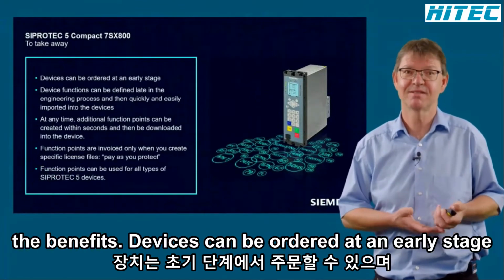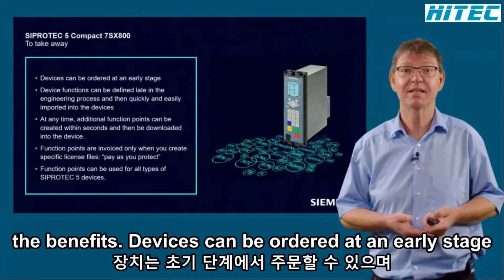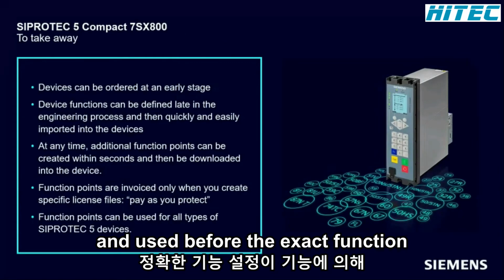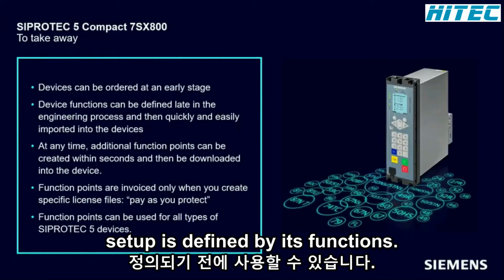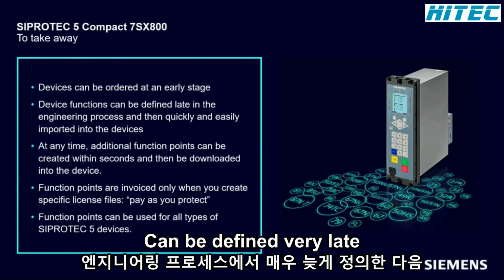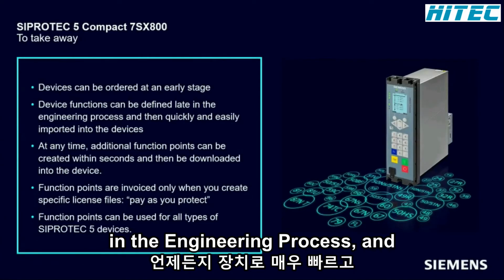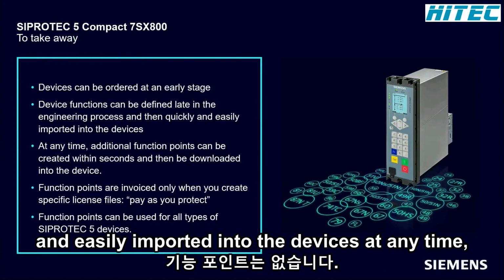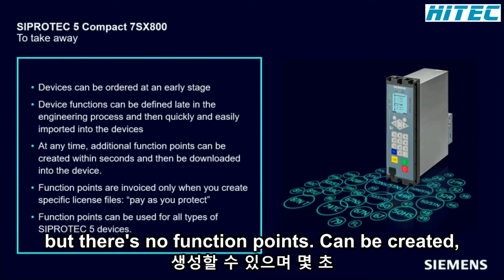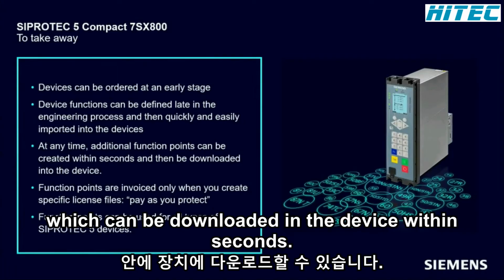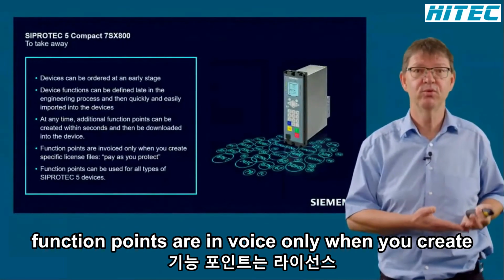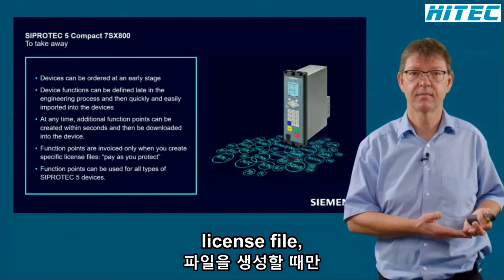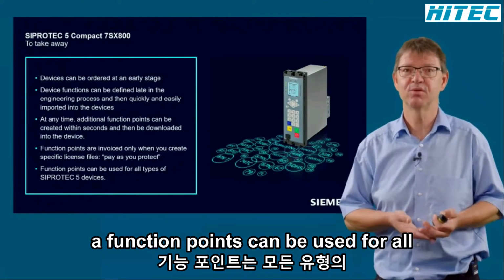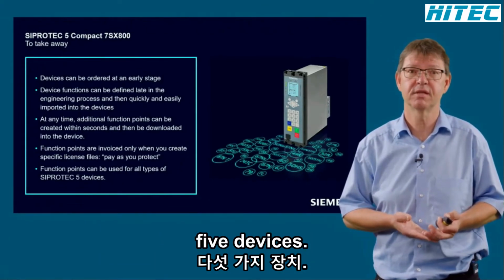Let's summarize the benefits. Devices can be ordered at an early stage and used before the exact function setup is defined. Device functions can be defined very late in the engineering process and then very quickly and easily imported into the devices. At any time, additional function points can be created, which can be downloaded in the device within seconds. Function points are invoiced only when you create license files. And by the way, function points can be used for all types of SIPROTEC 5 devices.